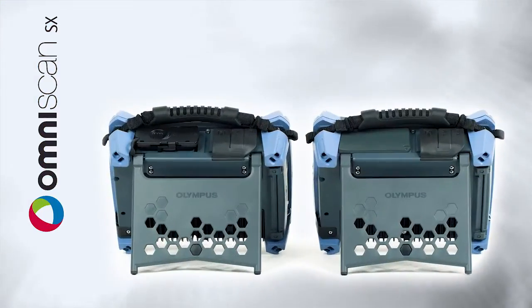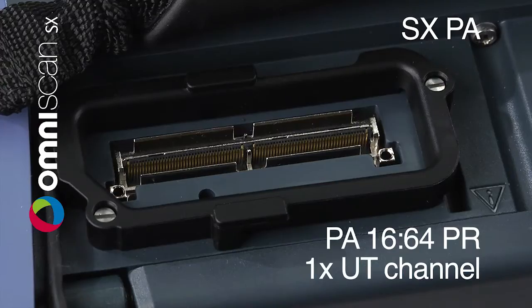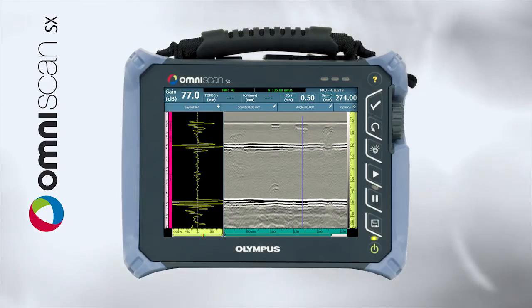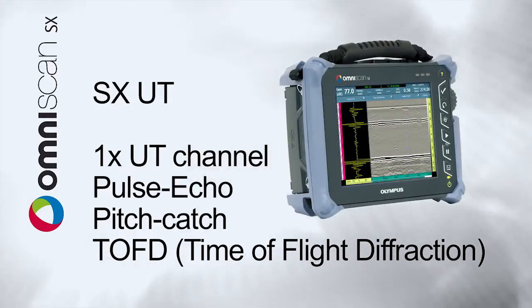The new OmniScan SX comes in two models, the SX PA and the SX UT. The SX PA is a 16:64 PR phased array unit. It is also equipped with a conventional UT channel which can perform TOFD technique. The SX UT is a non-PA version featuring the same conventional UT channel with identical capabilities.